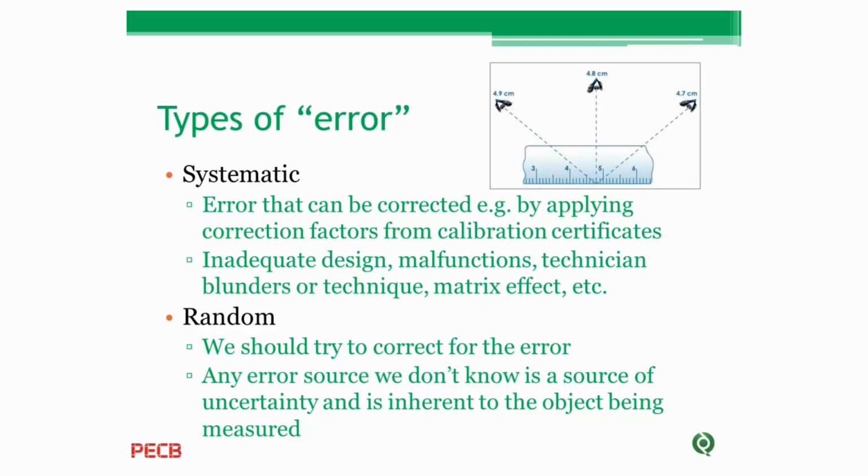Systematic error is an error which remains constant in replicates. It means that this error exists in your laboratory, and it is not a matter of replicating or increasing the number of the tests in your laboratories. Sometimes our equipment has some calibration correction factors which should be applied. When we don't apply them, systematic error happens.